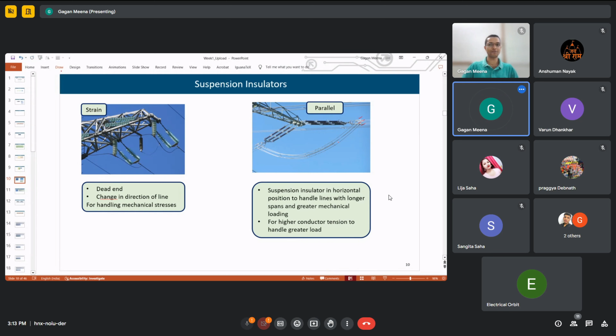This one is vertical, so mostly you will see vertical. But as a strain insulator, and when the loading is too much, these are also used in a horizontal way. Here in the second picture, because the line loading is too much, you can see that there are four conductors. It's a bundle conductor. Can you see four conductors? Is it visible? These are the four conductors. Here also you can see there are four conductors, a bundle of conductors. Because there are four conductors, the mechanical load increases as a result. To keep the tension, these suspension insulators are used in the horizontal way.